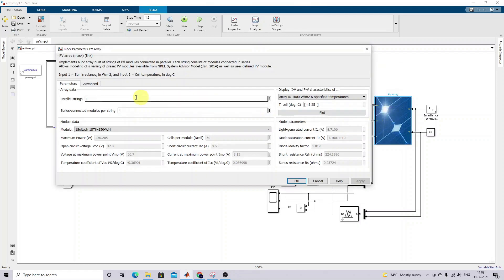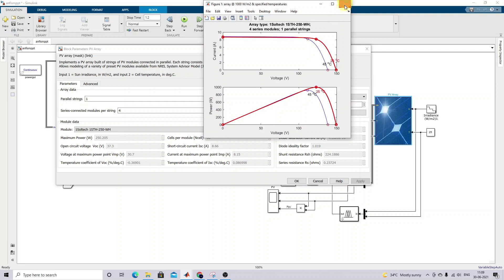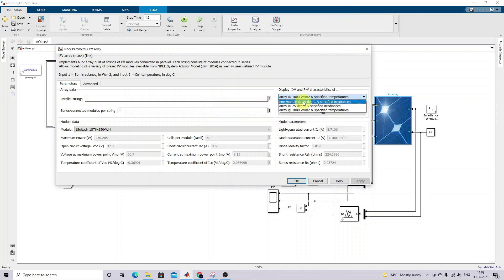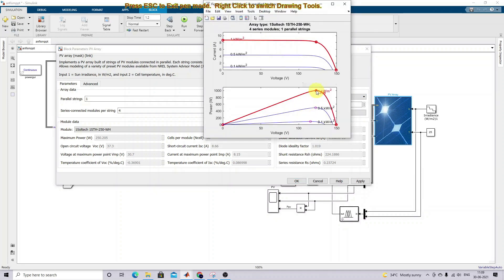Next, you have to design the LC values for a solar PV system. Here we are taking one parallel string and four series strings. The rating of a single panel is 250 watts, maximum voltage is 30.7V, and maximum current is 8.15A. When we plot the graph, the maximum power is around 1000W for 1000 W/m² and 500W for 500 W/m², varying according to irradiation.